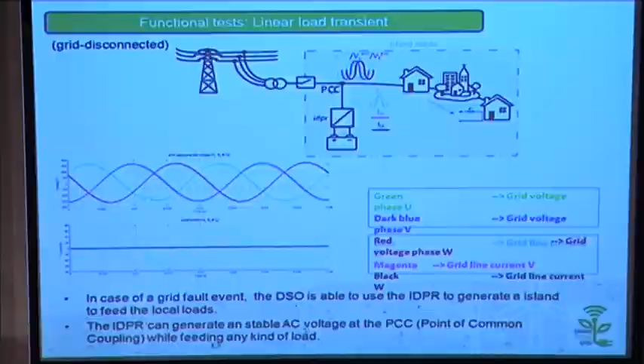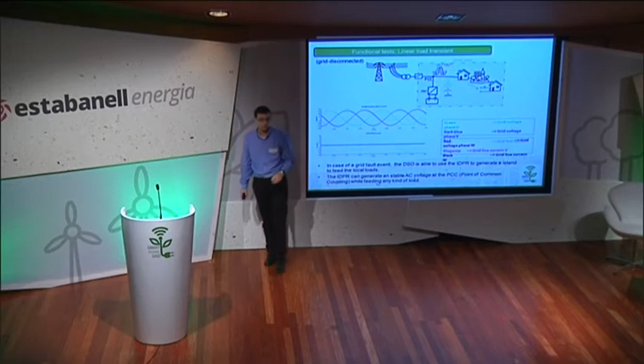These are also in the lab. In this case, these three waveforms represent the three voltages, and then we connect, in the worst case, more or less at the peak in terms of current, a heavy load. The IDPR is based on power electronics, so this means that we don't have the mechanical inertia that we would have if we were generating with a rotary machine. So we need to supply that current in a really fast way in terms of voltage, because the load will otherwise see a dip or a sag depending on whether we connect or disconnect the load. As you can see here, we are able to support that heavy consumption with just a really fast transient in terms of voltage. So this is good because we are supplying inertia in terms of current.